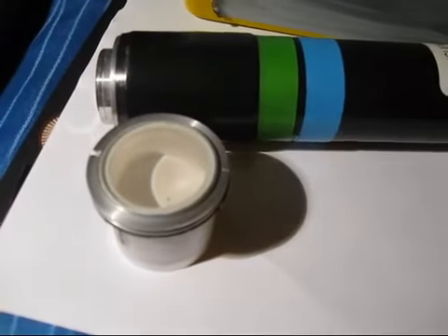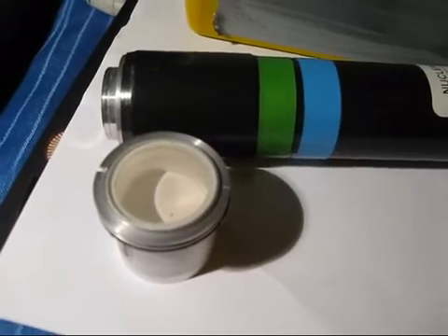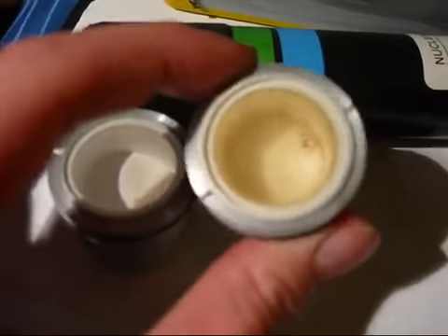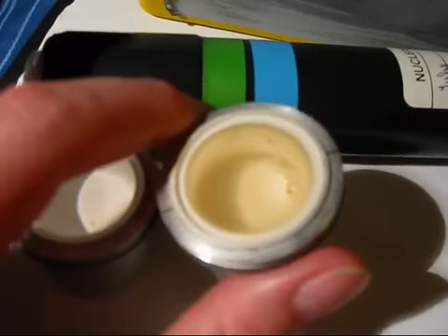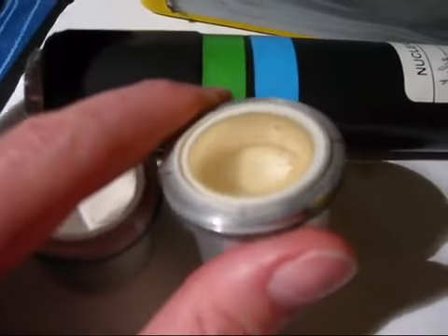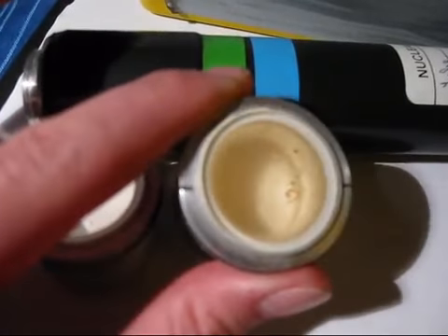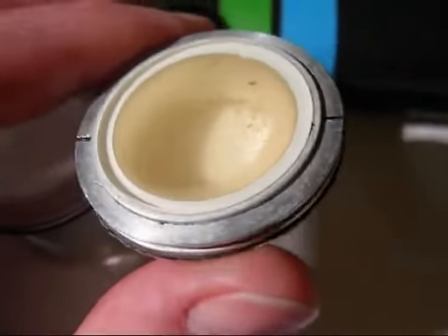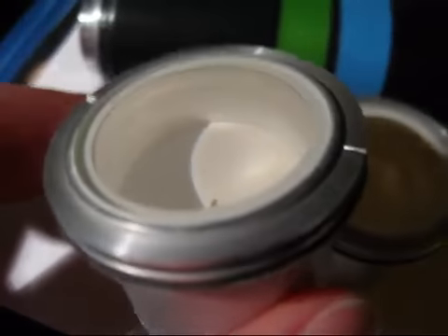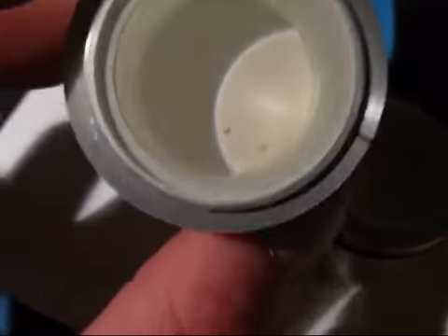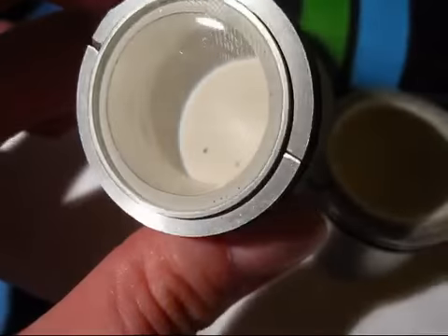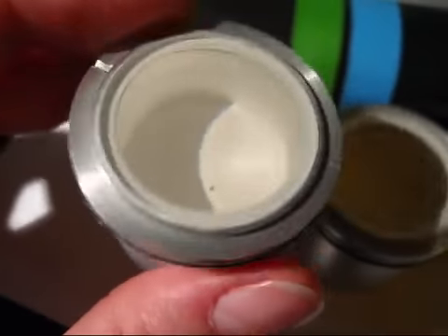You can see it a little better if I show you a crystal that has actually been damaged. There was a leak somewhere, so it took up air humidity, and thus it began to discolor, and you can sort of make out the structure of the crystal. Let's try this again with a closer focus, and you can see it's a pretty clear crystal with slight contaminations in there, but it's very clear. This is sort of like it ought to be.